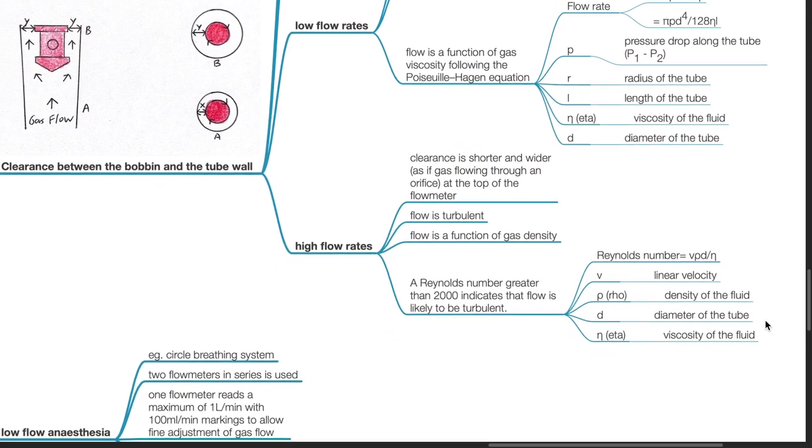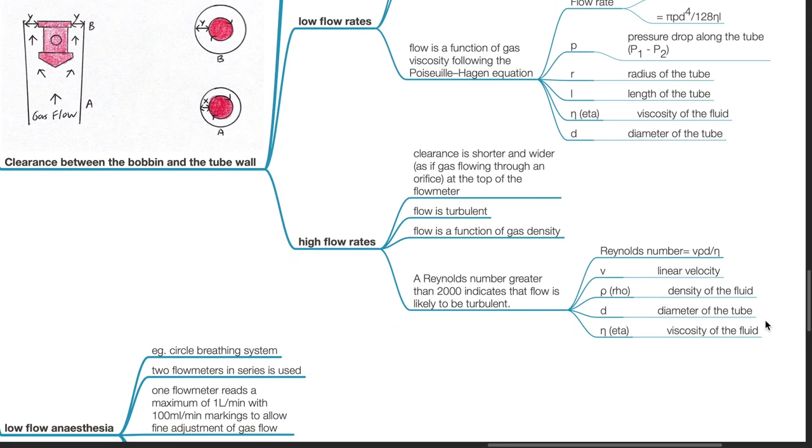At high flow rates, clearance is shorter and wider, as if gas flowing through an orifice at the top of the flow meter. Flow is turbulent and it is a function of gas density. A Reynolds number greater than 2000 indicates that flow is likely to be turbulent.